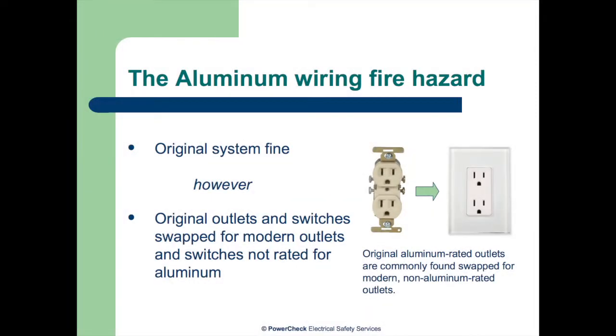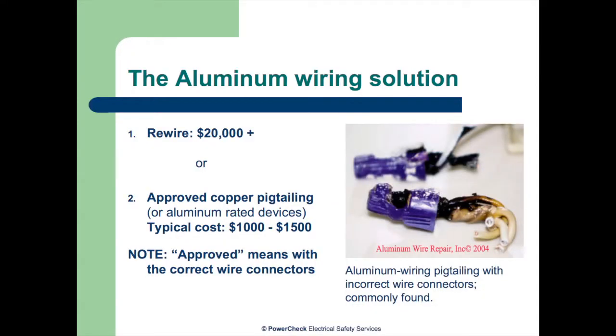Modern outlets are not rated for aluminum, they're rated for copper wire. It's the connection between the aluminum and the copper screws that causes the problems. Had they left it original, it would have been fine, but they didn't. They changed them for modern outlets. Again, the solution is pigtailing.